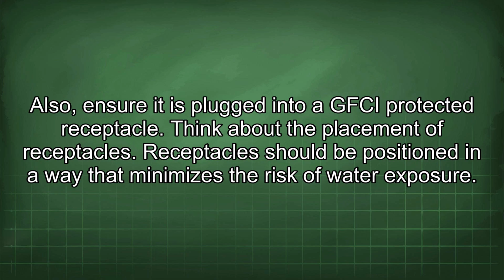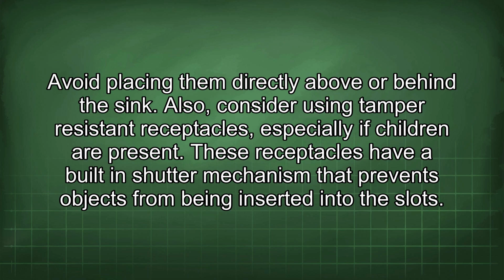Think about the placement of receptacles. Receptacles should be positioned in a way that minimizes the risk of water exposure. Avoid placing them directly above or behind the sink. Also, consider using tamper-resistant receptacles, especially if children are present. These receptacles have a built-in shutter mechanism that prevents objects from being inserted into the slots.